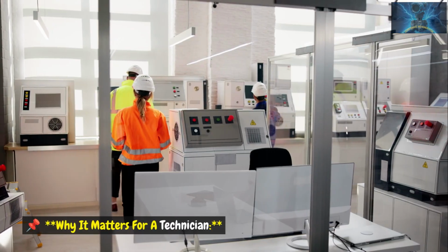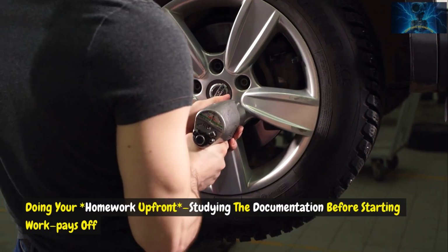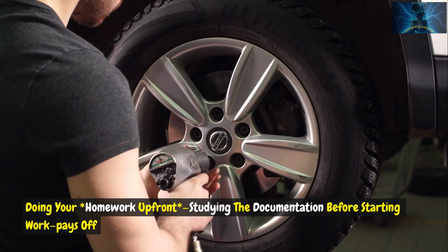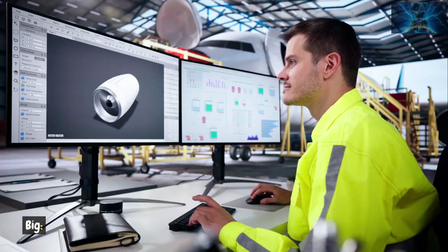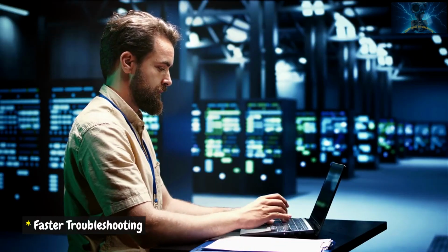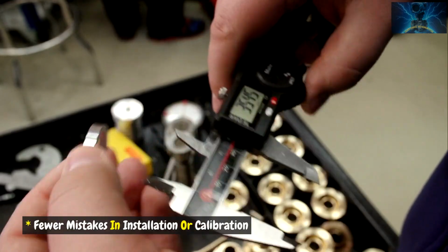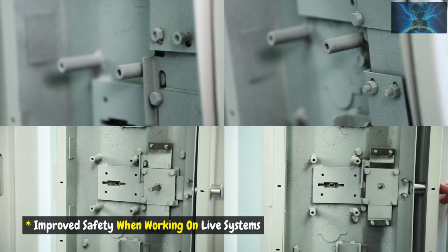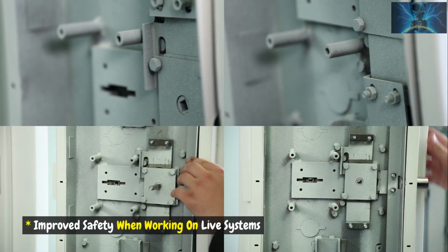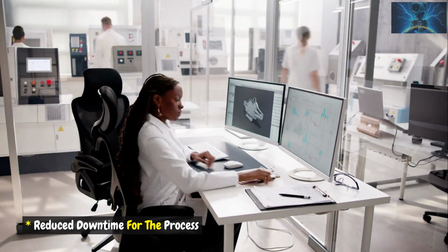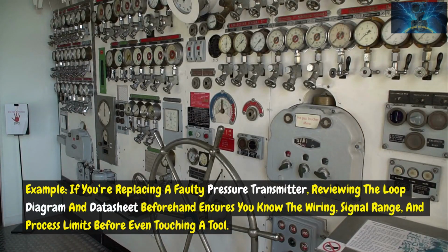Why does it matter for a technician? Doing your homework up front, studying the documentation before starting work, pays off big: faster troubleshooting, fewer mistakes in installation or calibration, improved safety when working on live systems, and reduced downtime for the process. For example, if you're replacing a faulty pressure transmitter, reviewing the loop diagram and datasheet beforehand ensures you know the wiring, signal range, and process limits before even touching a tool.